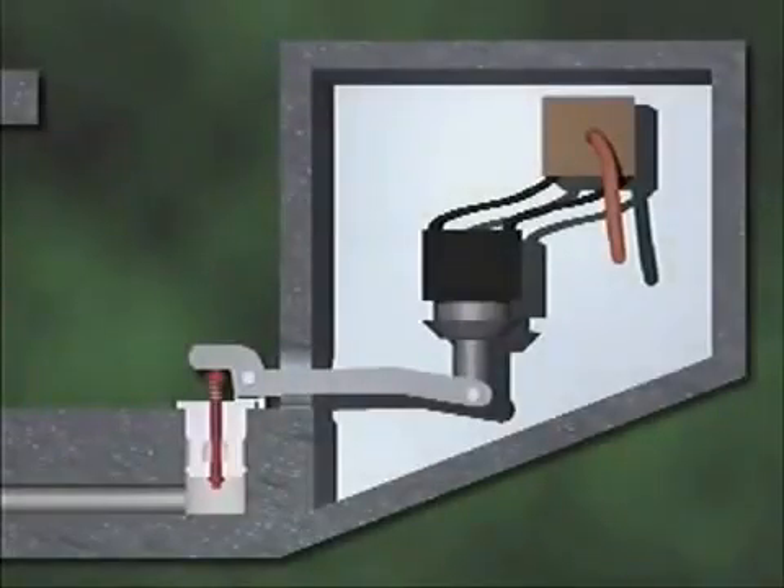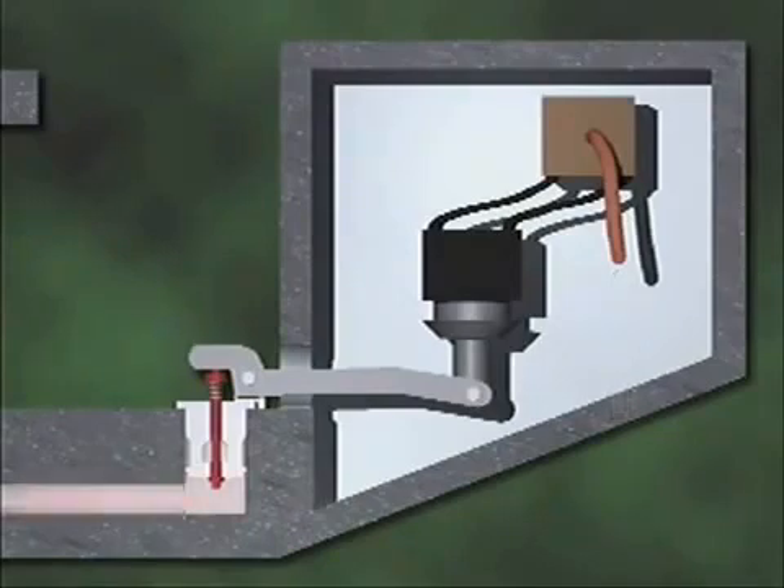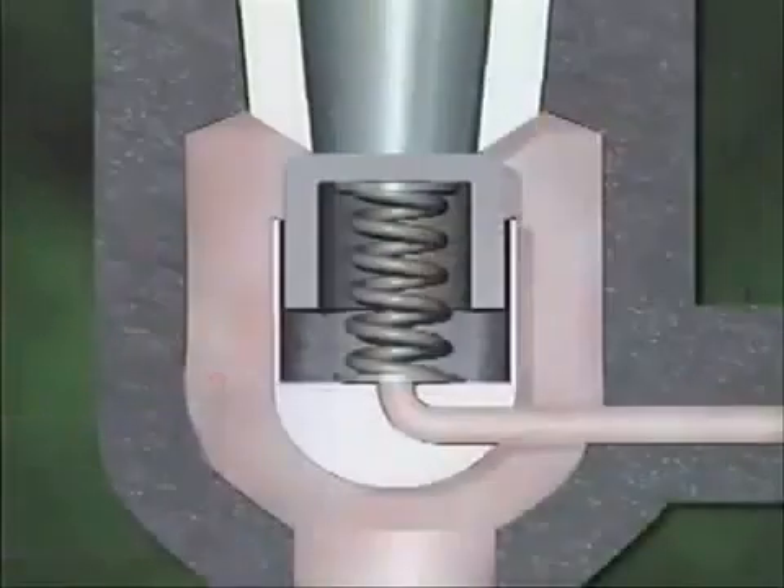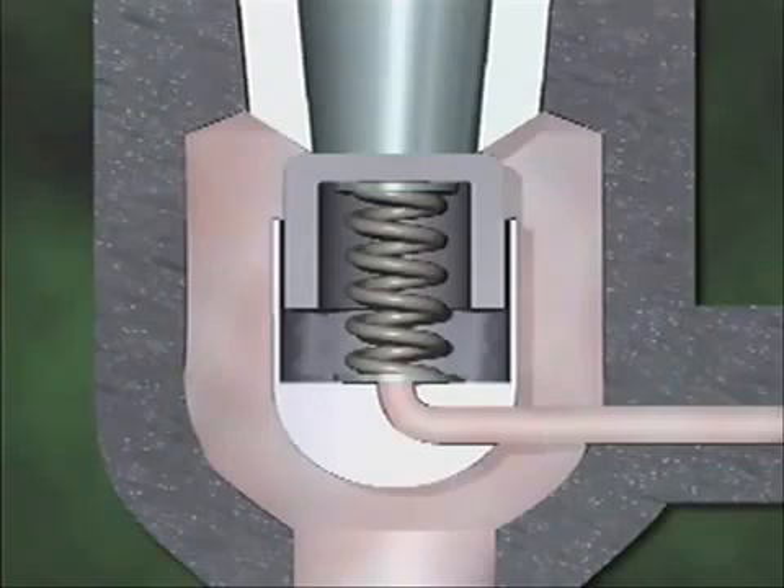The pilot device initiates the valve's opening. The device is set to open at a predetermined pressure. A pressure-sensing tube in the pilot device detects increases in system pressure, and when system pressure reaches the predetermined level, the pressure-sensing tube activates an electrical relay. The electrical relay closes an electrical circuit and energizes a solenoid. The solenoid then lifts a pilot valve and the excess pressure is relieved. The excess pressure relieved by the pilot valve comes from above the disc in the main valve, and the amount of pressure the pilot valve can relieve is greater than the amount that could leak between the disc and the disc guide.